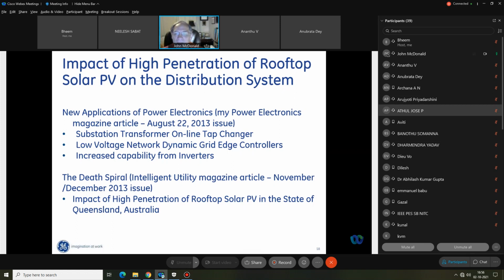In a substation, there's what we call an online tap changer. We want the voltage at the customer's home to be within a certain range, but we also want that voltage to be steady state, to be constant. Because if it isn't, if it changes quite a bit, the light bulbs in your house will be very bright, then very dim, changing all the time as the secondary voltage fluctuates. That would drive us crazy.